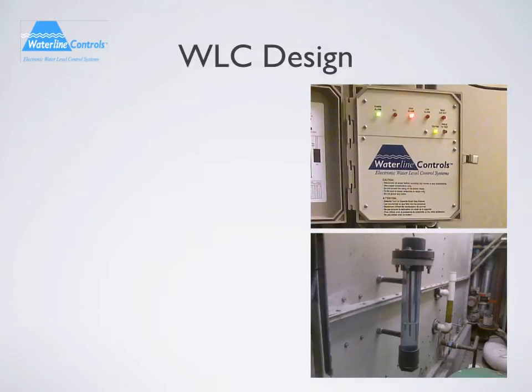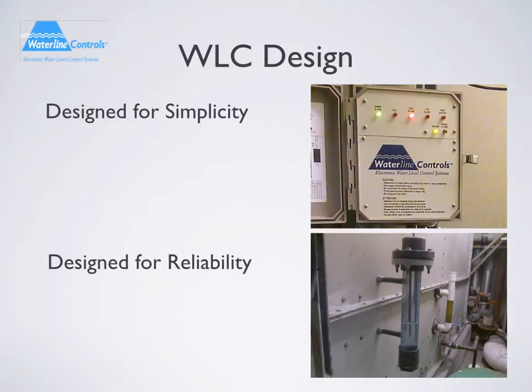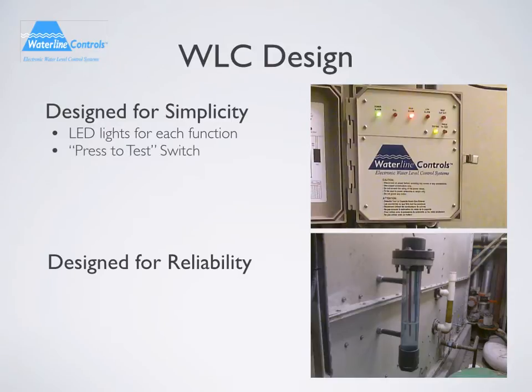When developing this technology, we wanted simplicity and reliability. Though each model is a little different, there are LED indicator lights for each function — when the LED is on, the device it operates is on. If there's an output relay, there is a status light for it. We included a press-to-test switch to make troubleshooting as simple as possible. Anyone can press the button, not take anything apart, and watch it cycle through each of the circuits for 15 seconds. The operator can immediately diagnose where the issue is, whether it is outside the controller, inside the controller, or something else entirely.